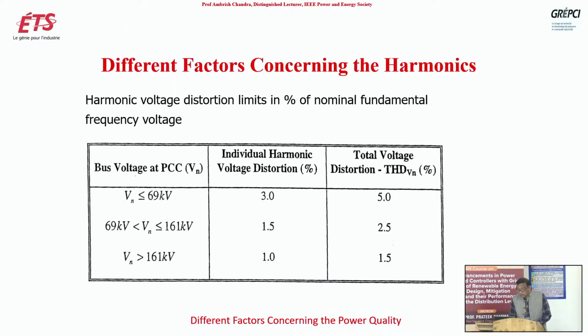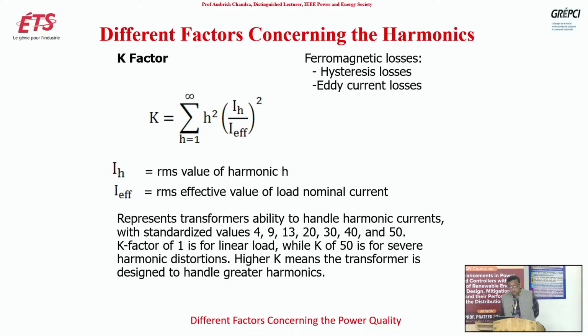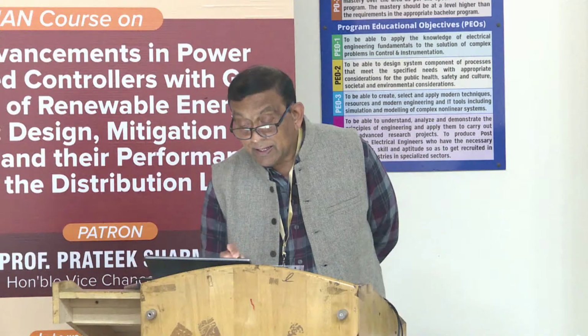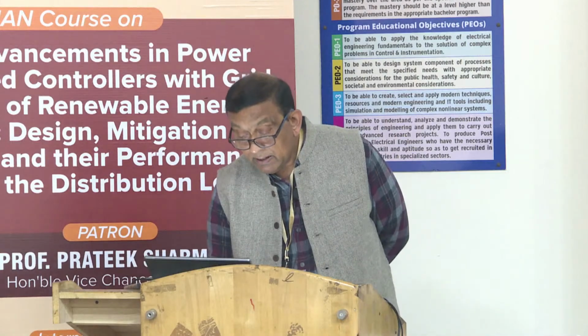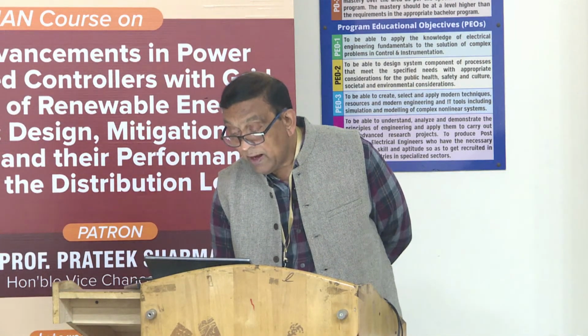Then we can talk about the K factor. This is the formula for K factor. Here I_h is the RMS value of harmonic h. And starting from 1 to, instead of infinity, we can put here the 50th harmonic. I effective is the RMS effective value of load nominal current. So what is basically factor K? It represents the transformer's ability to handle harmonic currents.